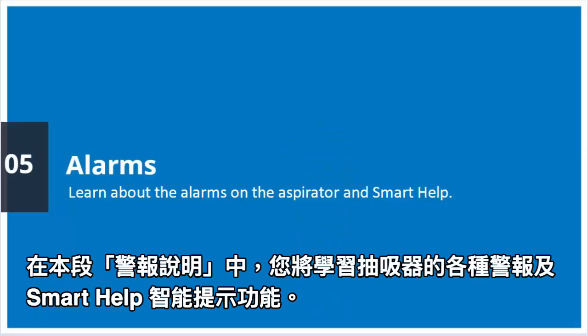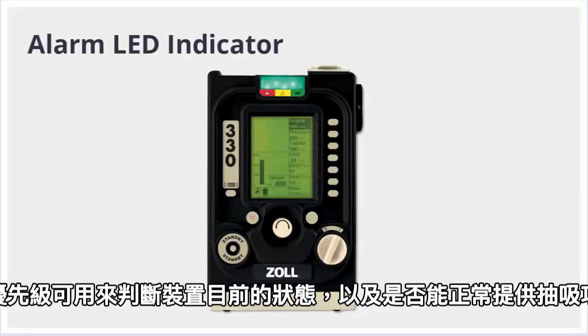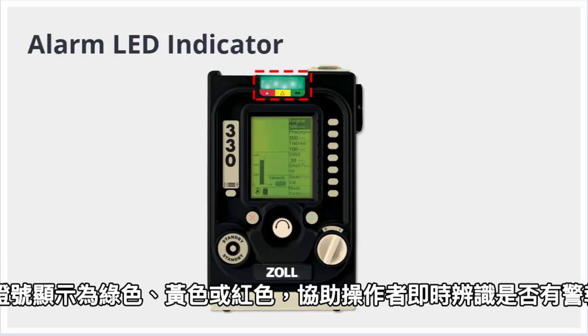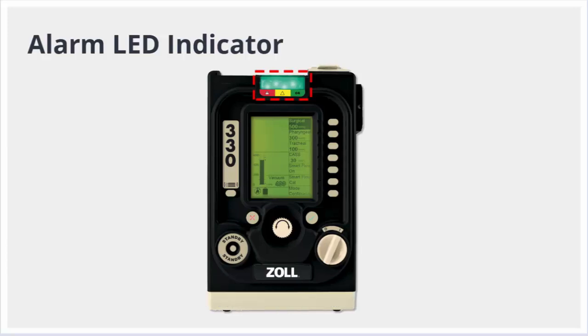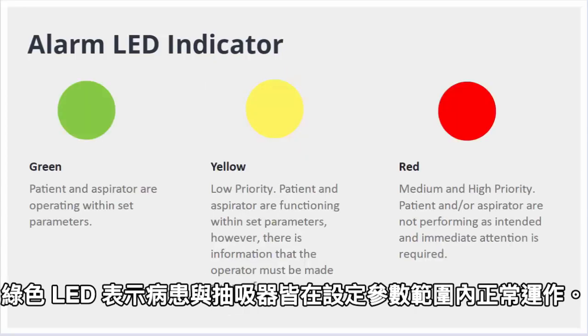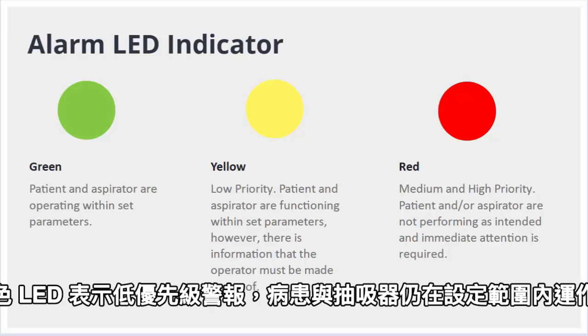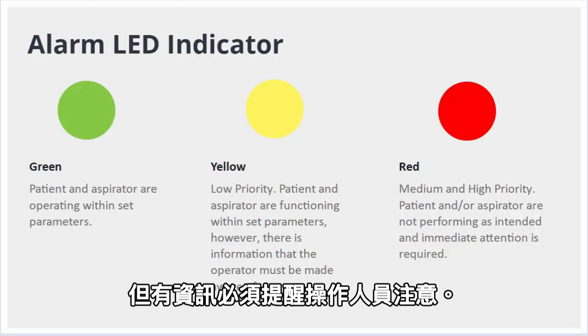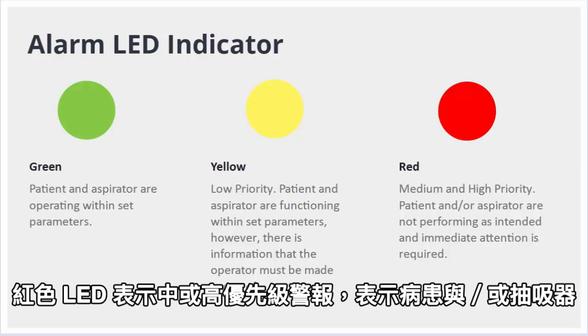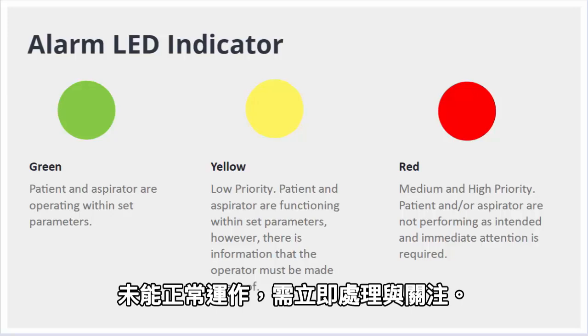In this alarm section, you will learn about the alarms on the aspirator and Smart Help. Alarm priorities define the status of the device and the ability of it to provide suction. The LED displays green, yellow, or red lighting to help the provider know if there is an alarm present. The green LED indicates the patient and aspirator are operating within set parameters. The yellow LED indicates a low priority alarm. The patient and aspirator are functioning within set parameters. However, there is information that the operator must be made aware of. The red LED indicates both medium and high priority alarms. The patient and/or aspirator are not performing as intended, and immediate attention is required.